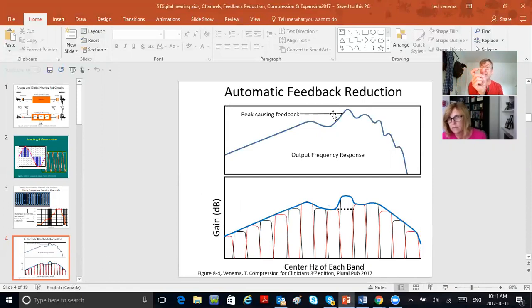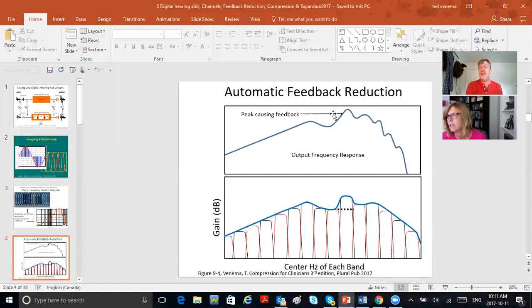Then there are roving notch filters — they move. Wherever there's a high-frequency peak, the notch filter moves there and knocks it out. The hearing aid is digitally programmed to detect wherever there's a high-frequency peak, go over there and put out that fire.